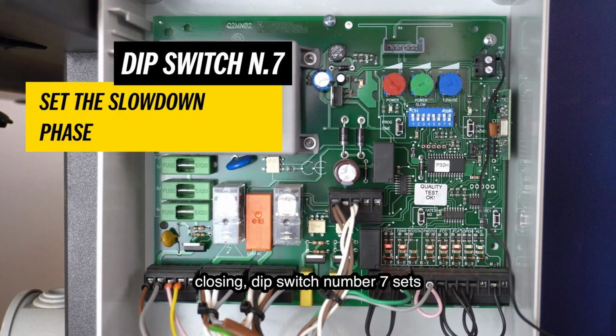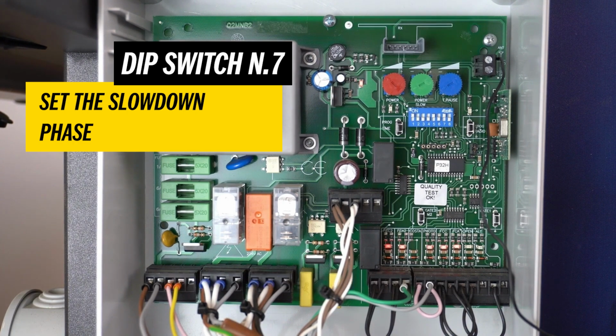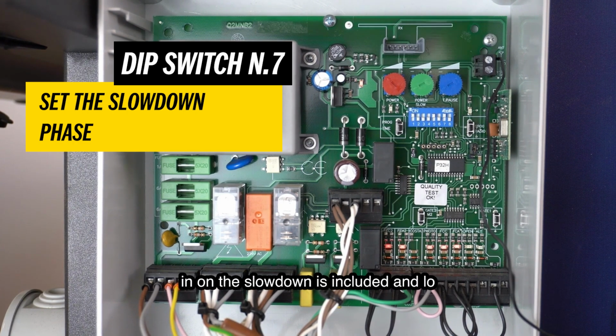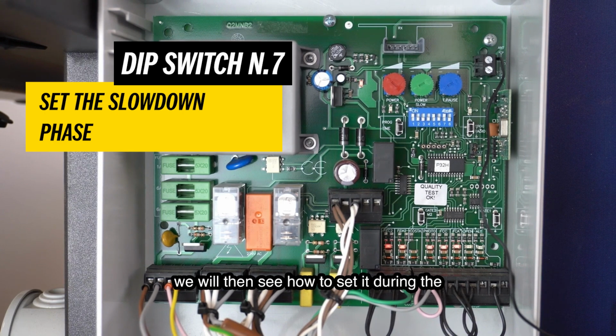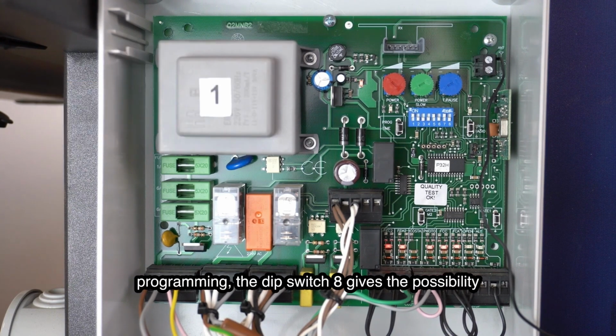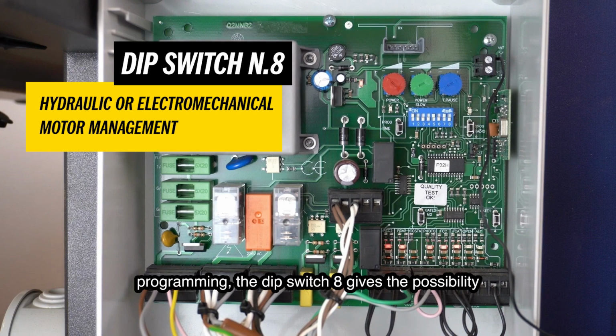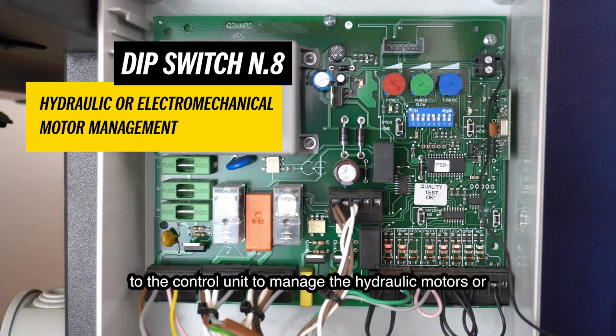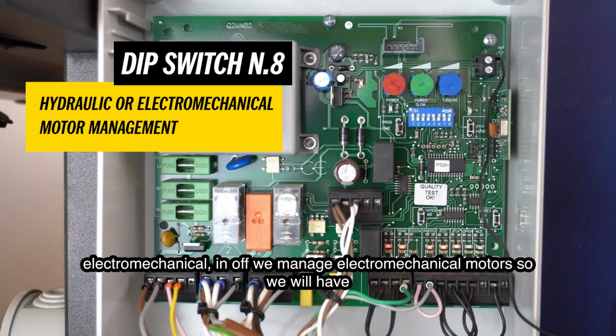for closing. Dip switch 7 sets the slowdown: off, the slowdown is excluded, and on, the slowdown is included. We will then see how to set it during the programming process. Dip switch 8 provides the possibility to set the control unit for hydraulic or electromechanical motors.